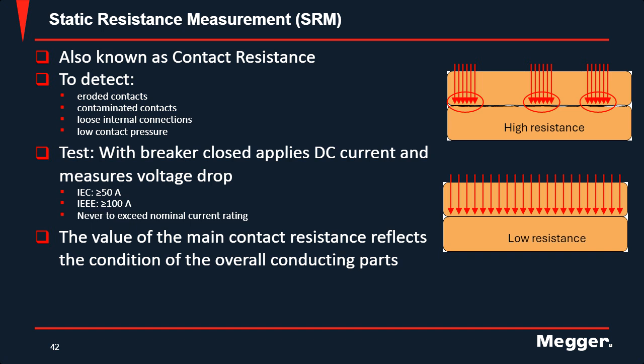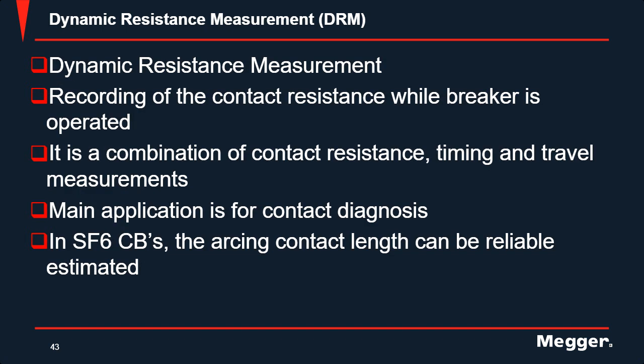And then ANSI specifies that you should use a minimum of 100 amps. So just based off where you're located, make sure that you're using a high enough value so that you're not getting anomalous results that are high just because you're not using enough current. So that was contact resistance. There's not much to it. It's just putting current on the circuit with the breaker closed, and it monitors the voltage drop and then calculates your resistance. Now, dynamic resistance measurements.